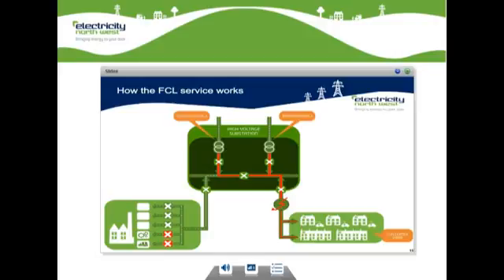Once the fault section has been isolated, the motor and generator can be switched back on. During this time, the rest of the customer's equipment would remain on as normal. Only the selected items of plant would be interrupted, and only until we have disconnected the fault and put our system back to normal, which would normally be up to about 5 minutes.